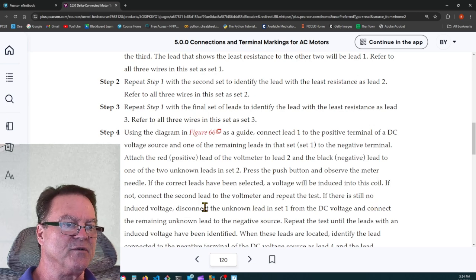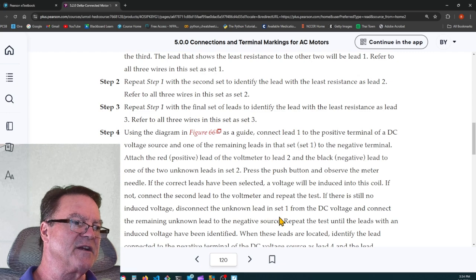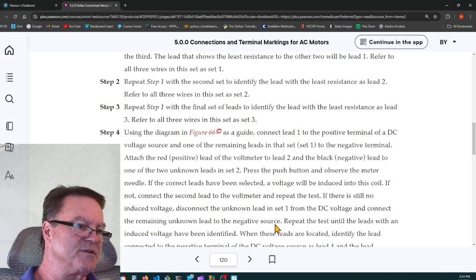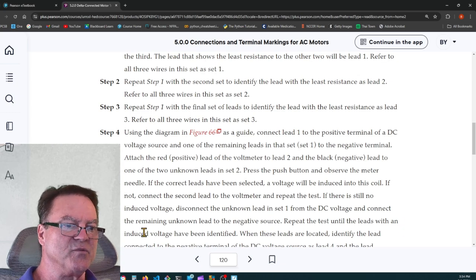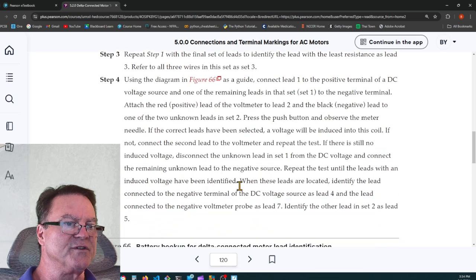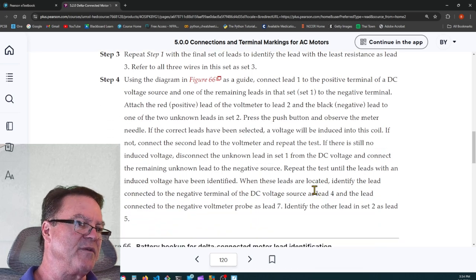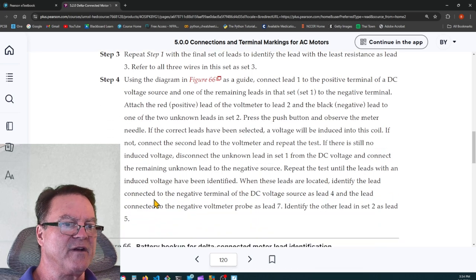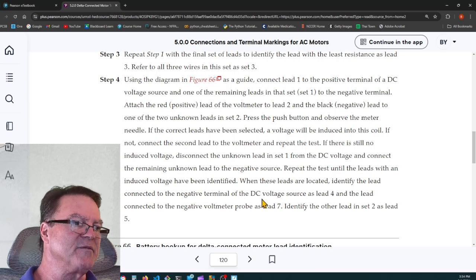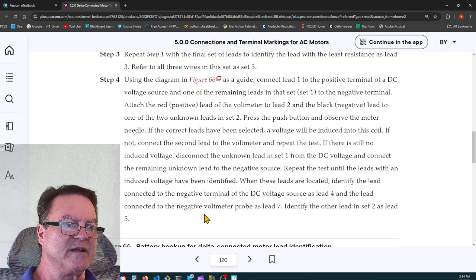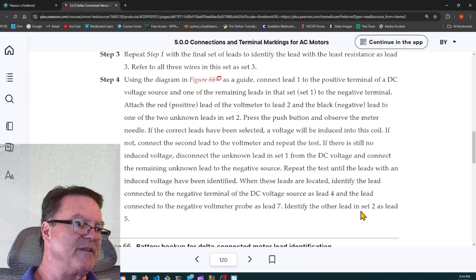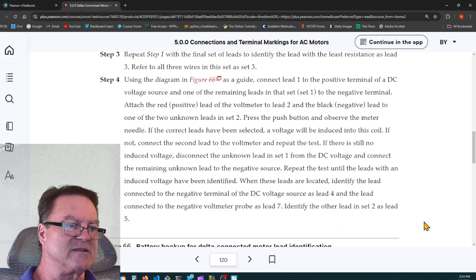If there is still no induced voltage, disconnect the unknown lead in set 1 from the DC voltage and connect the remaining unknown lead to the negative source. Repeat the test until the leads with an induced voltage have been identified. When these leads are located, identify the lead connected to the negative terminal of the DC voltage source as lead 4 and the lead connected to the negative voltmeter probe as lead 7. Identify the other lead in set 2 as lead 5.